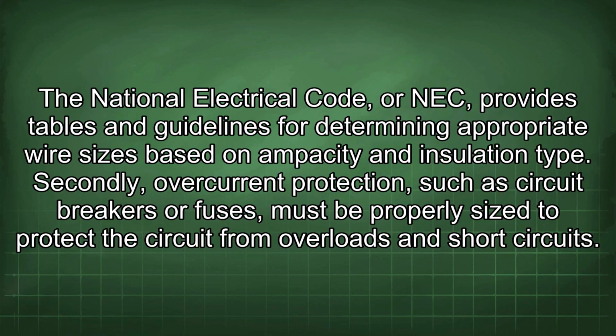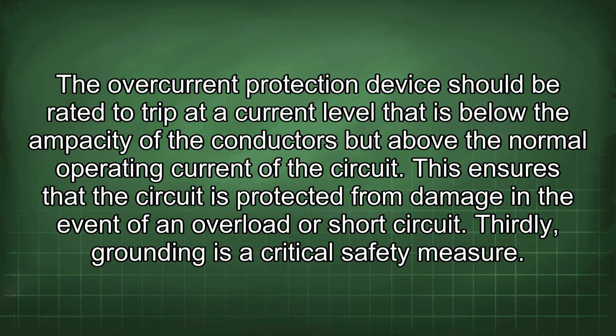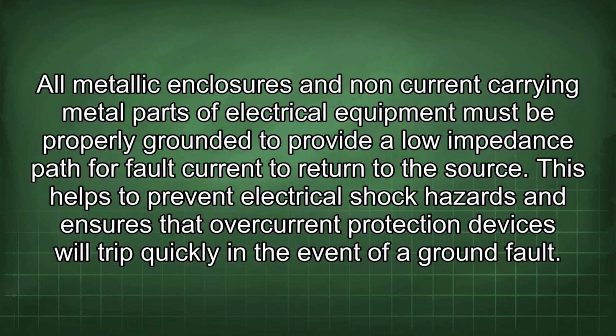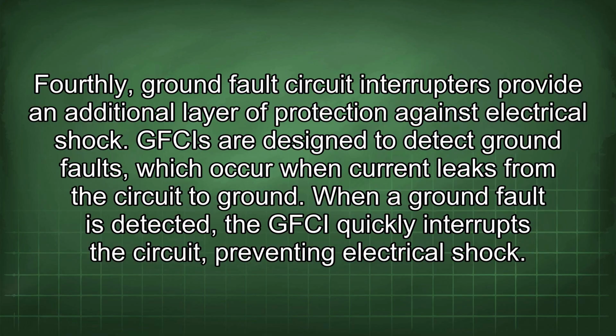and short circuits. The overcurrent protection device should be rated to trip at a current level that is below the ampacity of the conductors but above the normal operating current of the circuit. This ensures that the circuit is protected from damage in the event of an overload or short circuit. Thirdly, grounding is a critical safety measure. All metallic enclosures and non-current carrying metal parts of electrical equipment must be properly grounded to provide a low impedance path for fault current to return to the source. This helps to prevent electrical shock hazards and ensures that overcurrent protection devices will trip quickly in the event of a ground fault.